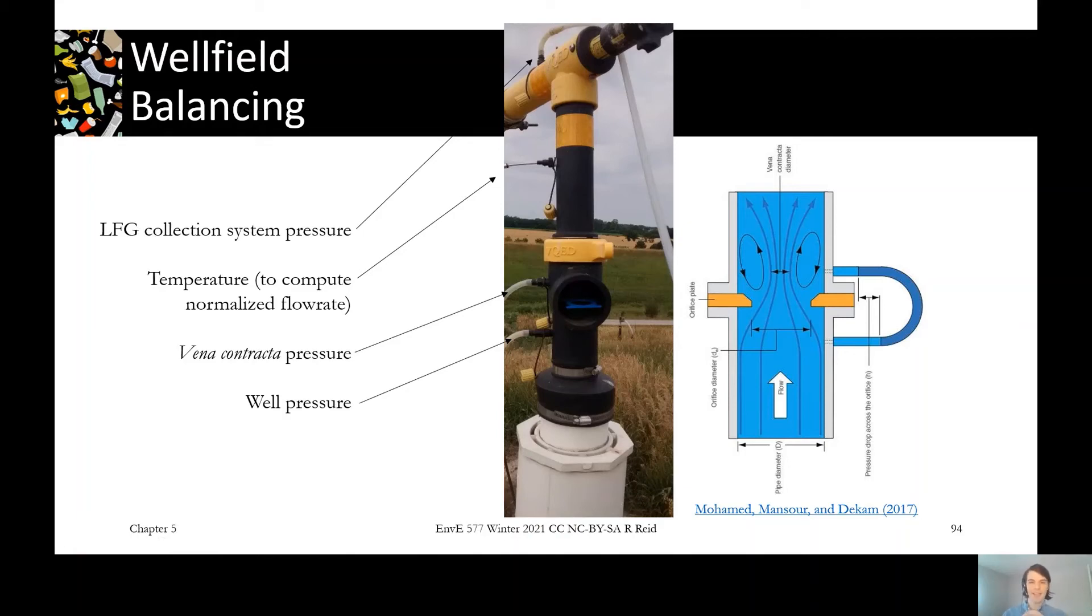So as a landfill gas technician doing this balancing, you'd be coming to your well, you'd measure all these pressures, calculate the flow rate and then look at based on the gas quality you measured, does it look like this well needs to be pulling more gas or less gas and then adjusting that valve to make that change.